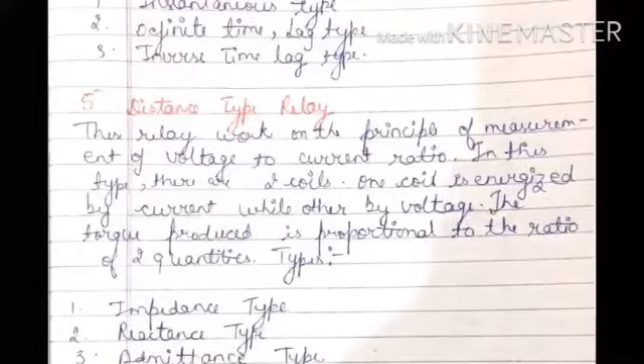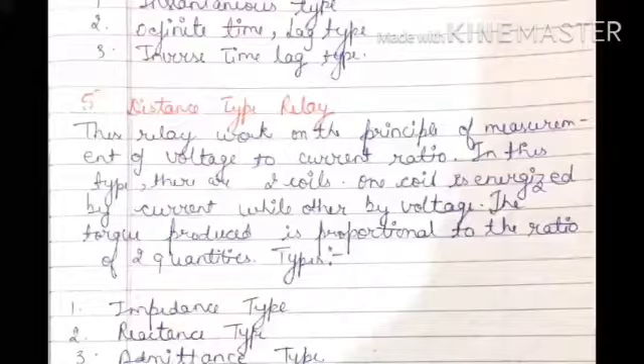To summarize the timing types: instantaneous means as soon as the fault occurs and my coil trips, the circuit breaker opens with negligible operation time. Definite time means there is an intentional time lag between the trip coil operating and the circuit breaker performing its operation. Inverse time means the operating time is approximately inversely proportional to the magnitude of the actuating quantity.